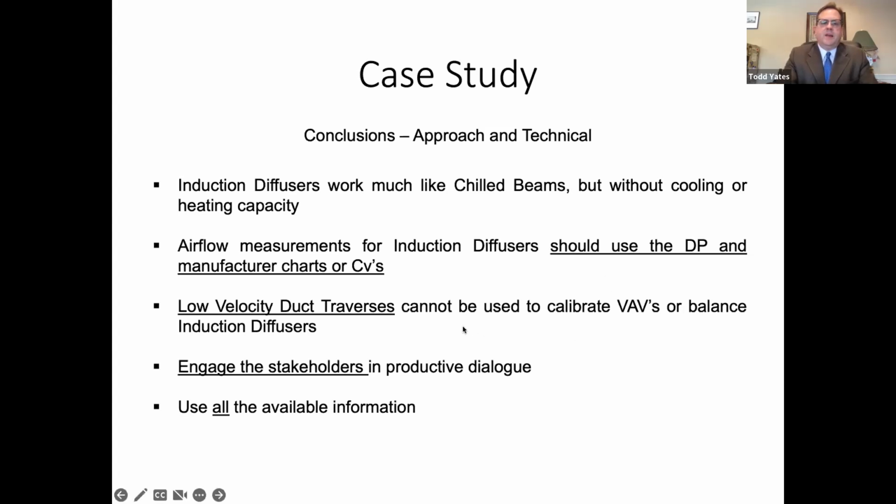Yeah, and we didn't get much feedback from the manufacturer after we got past that initial conversation, that meeting I described where everyone was there, and at least that representative pretty much just said, you have to do it with the differential pressure drop, and that's it. That's the only thing that's acceptable.